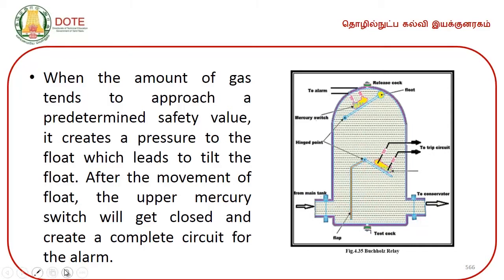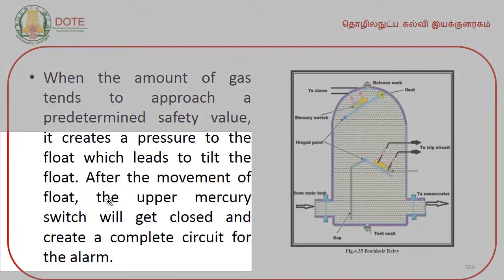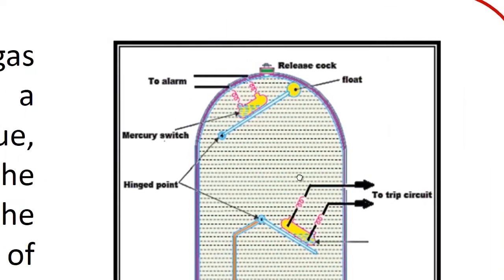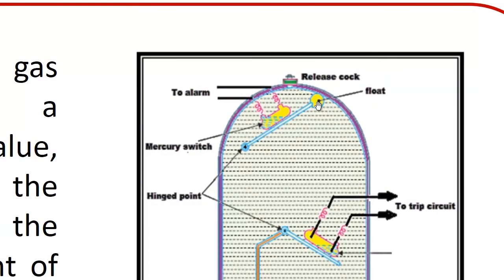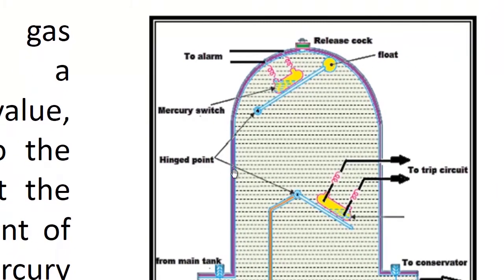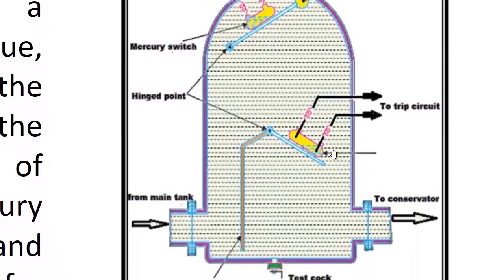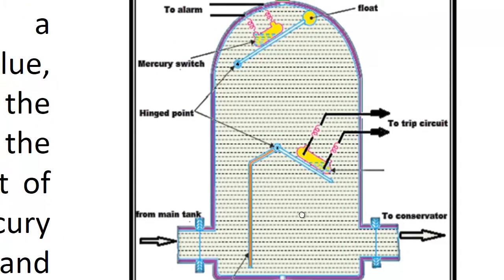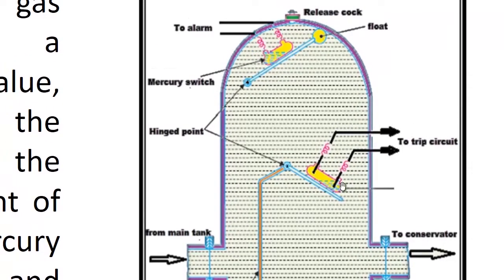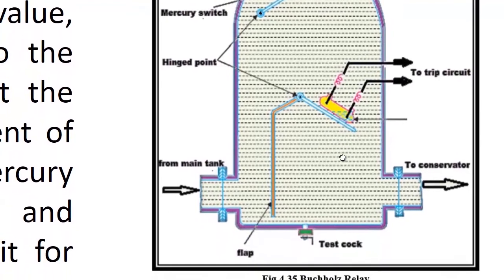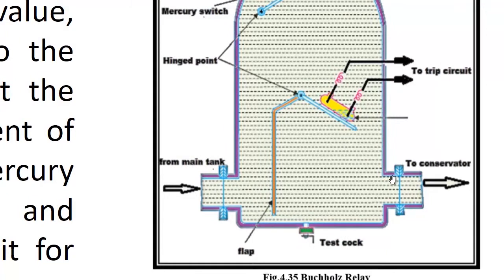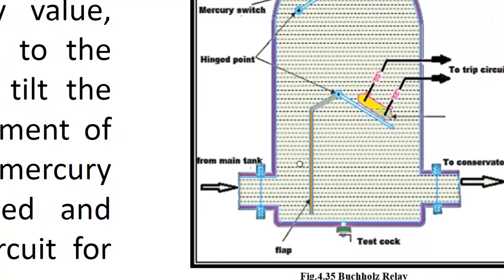I will zoom this in. You can see here. So, this is to alarm, this is the float, and this is the mercury switch, hinged point, and to trip circuit. Whenever this mercury switch is closed, this will issue a signal to the trip circuit to trip it. So, this is from the main tank, this is the passage to the conservator. This is the test cock which can be removed to refill the oil, or to filter the oil, etc. And this is the flap which holds the trip circuit arrangement.